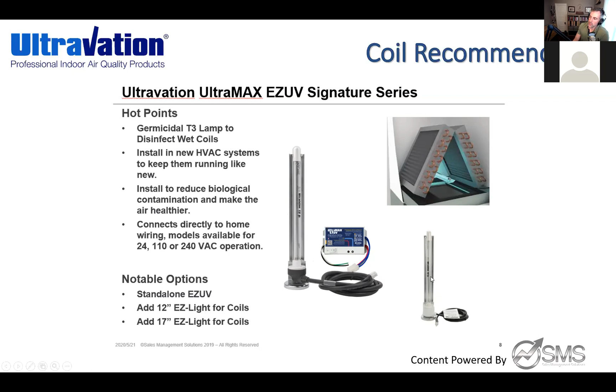And then, as I hinted at earlier, there's different classes of UV. This is our product that actually uses UVA inside of the filter cabinet with our MERV 11 filter. But we also have a slide-in PCO titanium dioxide coated screen here. So as the air passes through the filter, then it passes by the UVA lamps, which are activating the PCO screen. And again, because it's in such proximity to the filter, we're not using a UVC class lamp. So to stay aligned with ASHRAE's guidelines, we also give the ability to add on UVC wavelength lamps to put on the coil.